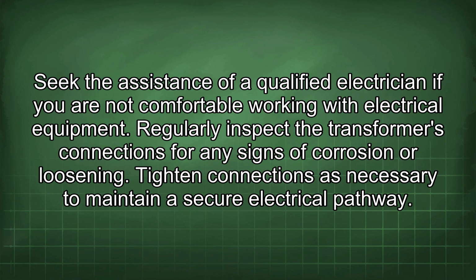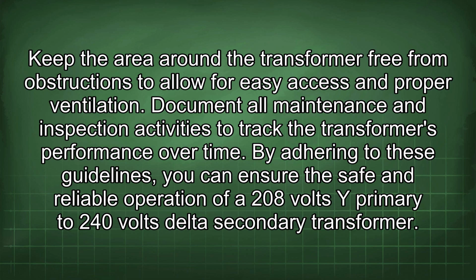Regularly inspect the transformer's connections for any signs of corrosion or loosening. Tighten connections as necessary to maintain a secure electrical pathway. Keep the area around the transformer free from obstructions to allow for easy access and proper ventilation. Document all maintenance and inspection activities to track the transformer's performance over time.